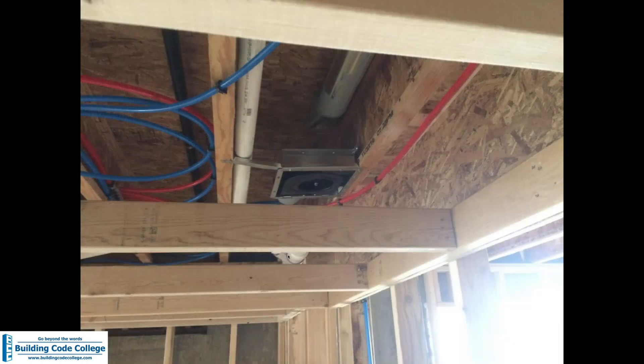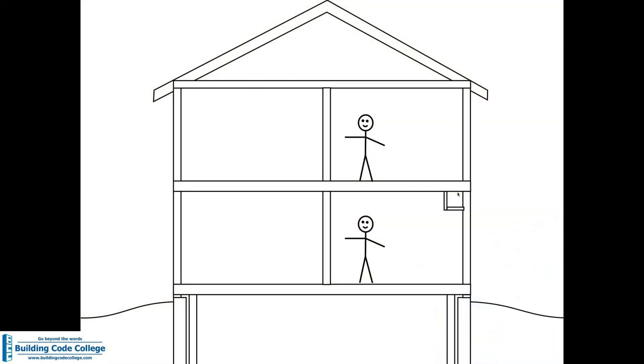The other scenario is a dropped ceiling below a floor system. In this example, a bathroom in the basement has a dropped ceiling below the bottom of the I-joists, which creates a floor-ceiling cavity that's now wide open. They probably should move that bath fan down to the level of the dropped ceiling. Draft stopping applies to floor assemblies where there's a floor above and a ceiling below — it's a concealed space. Draft stopping and fire blocking are both about slowing fire spread in concealed spaces that we can't see.